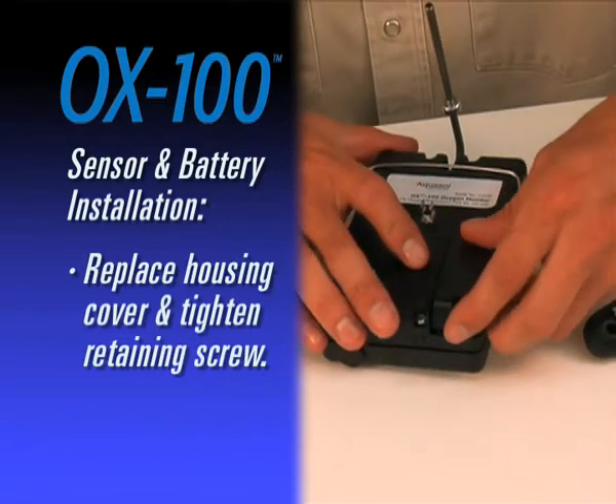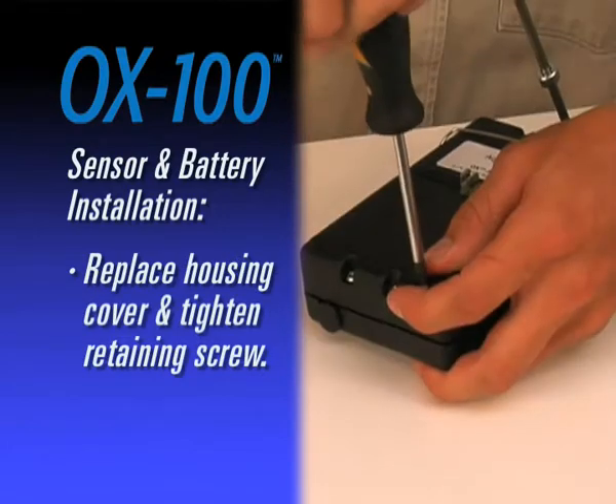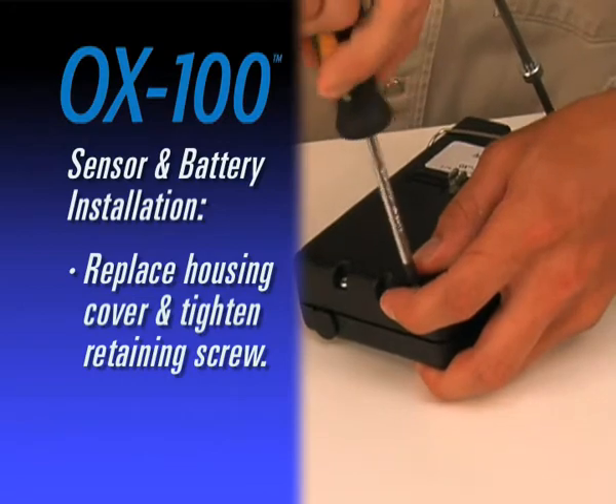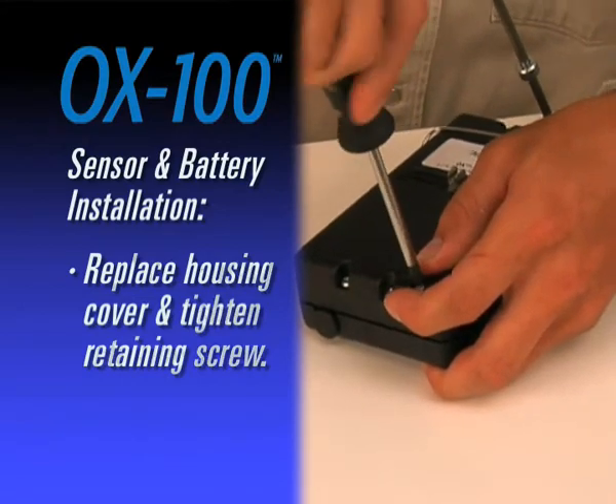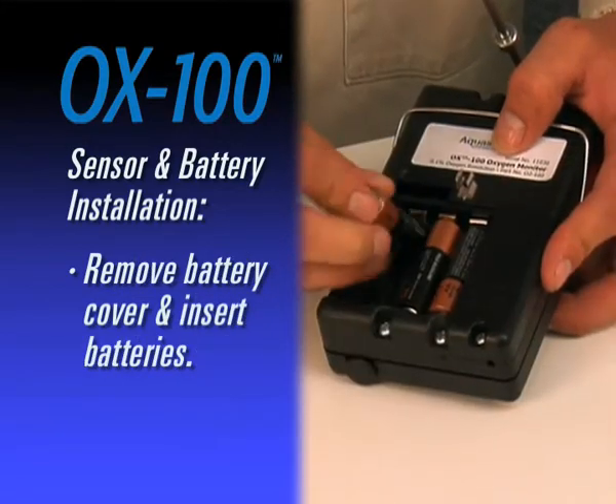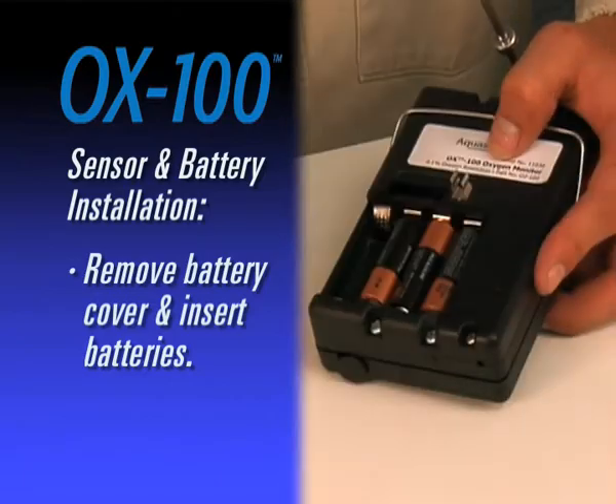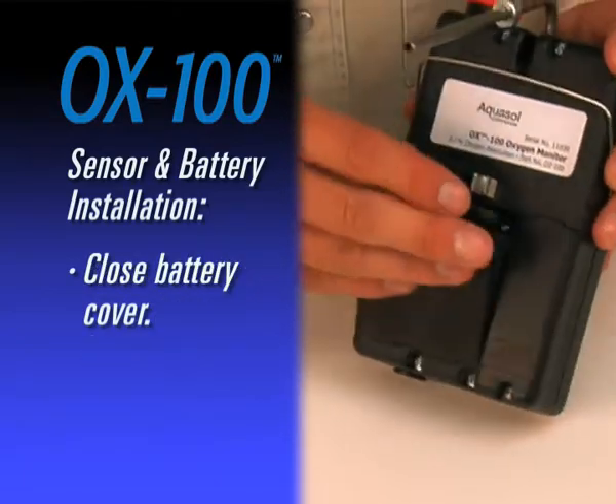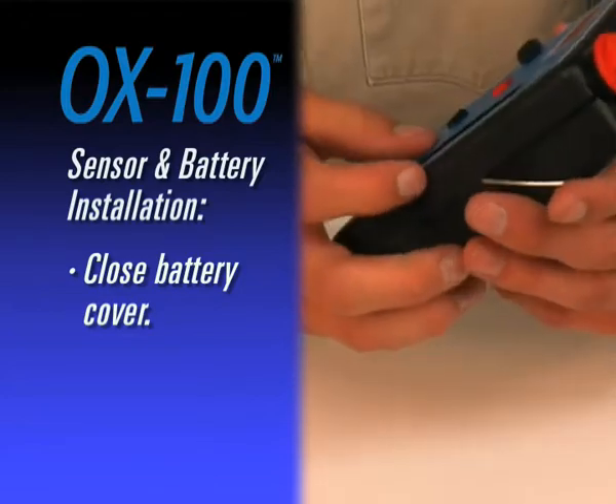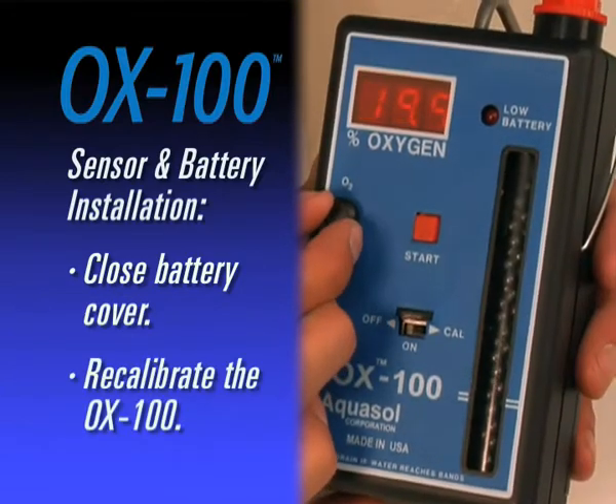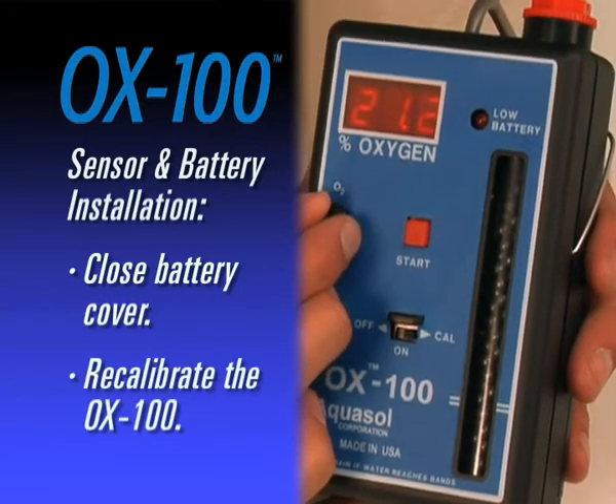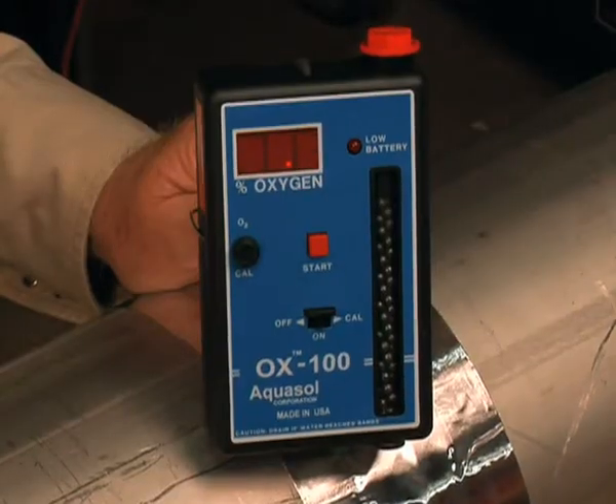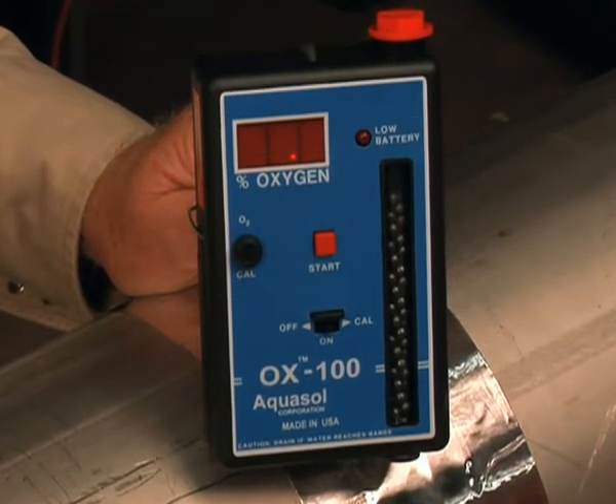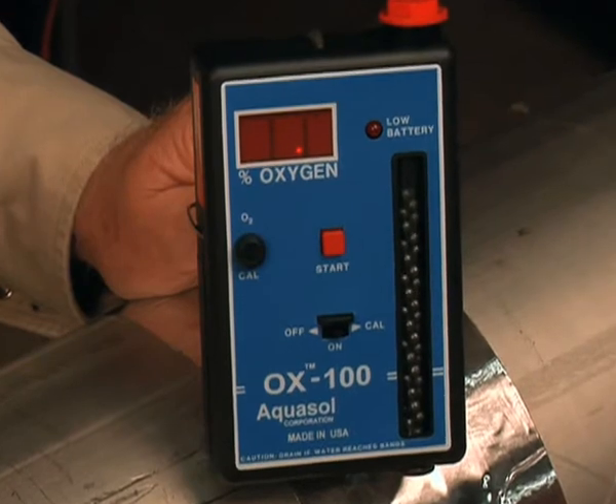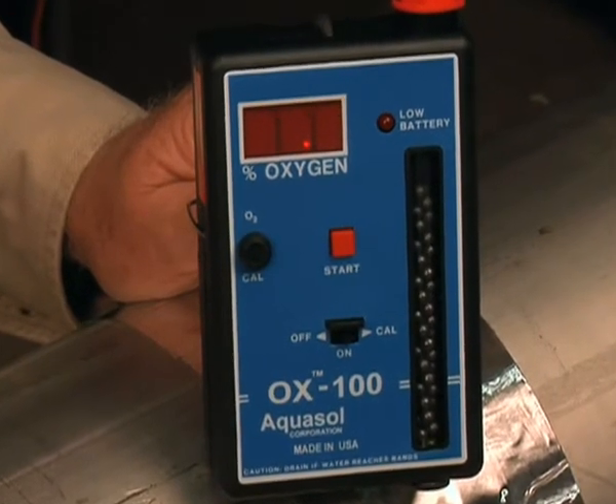Replace sensor housing cover and tighten retaining screw with a Phillips head screwdriver. Remove battery cover and insert 4 AA batteries. Close the cover on the battery house. Finally, recalibrate the OX-100. With the sensor installed, detecting oxygen levels with the OX-100 can be achieved following a few simple steps.